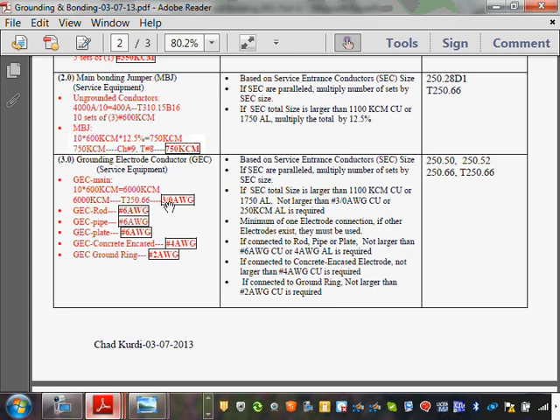Where did I get all this info? Right from here. When I say not smaller, guys, you can always go higher. So all these little grounding electrode conductors that tie into the bar do not need to go larger than these. Any comments, guys, about the grounding electrode? I pulled this information from these articles, and I'll let you read it on your own. Any comments?